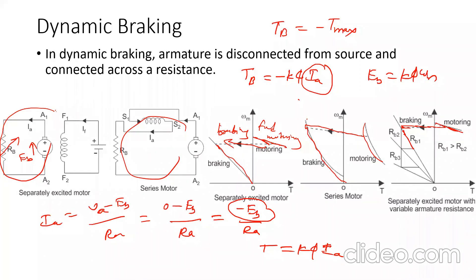Because of the braking, the characteristic shifts from motoring to braking region. Due to the high resistance in the braking circuit the speed falls sharply, with resistance equal to Rb1. To maintain the same maximum torque, some resistance is cut off so current rises again and braking torque rises — the speed drops sharply with resistance Rb2. Again, some part of resistance is cut off, current rises, braking torque rises, and the speed falls sharply once more.